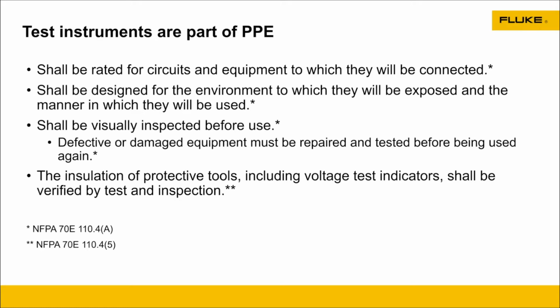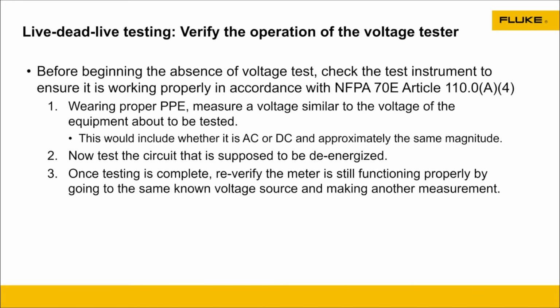I've heard countless times about people being shocked because their meter wasn't working correctly. They thought that the circuit was dead. They went ahead and took their gloves off, they started working on it, and then realized that it was actually a live measurement. So how do we even test our DMM? How do we check that? Well, part of NFPA 70E says we need to do a live dead live test. We're validating that the meter is going to work correctly.